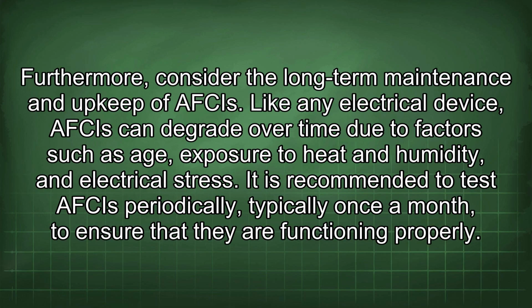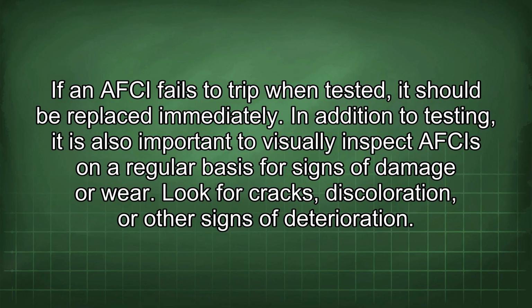Furthermore, consider the long-term maintenance and upkeep of AFCIs. Like any electrical device, AFCIs can degrade over time due to factors such as age, exposure to heat and humidity, and electrical stress. It is recommended to test AFCIs periodically, typically once a month, to ensure that they are functioning properly. If an AFCI fails to trip when tested, it should be replaced immediately. In addition to testing, it is also important to visually inspect AFCIs on a regular basis for signs of damage or wear.